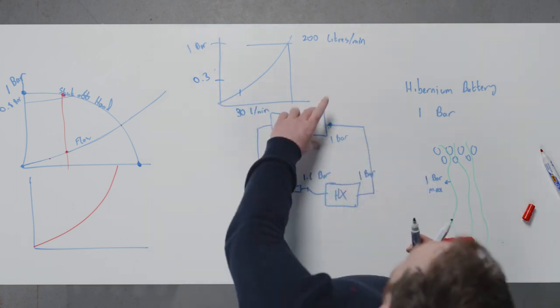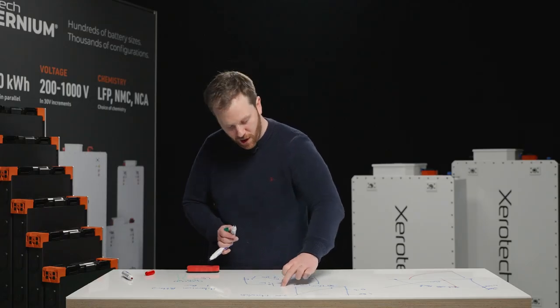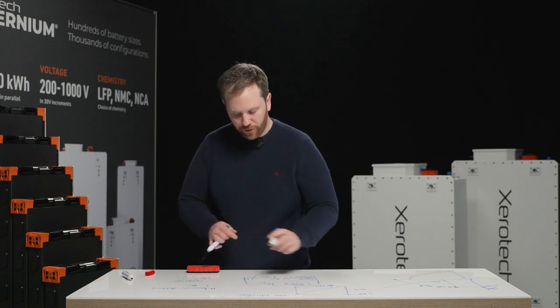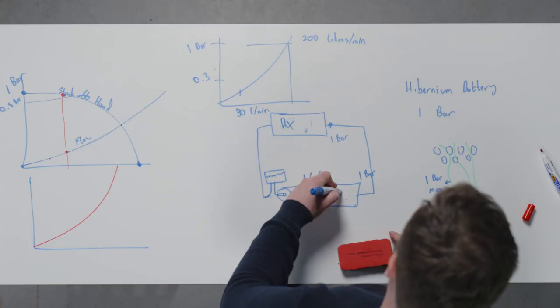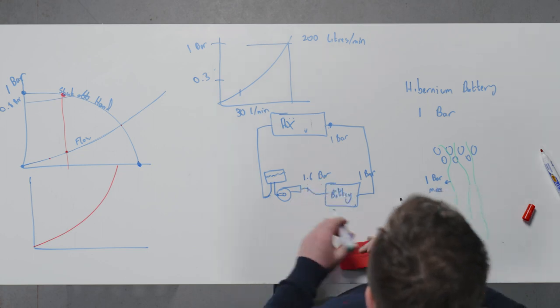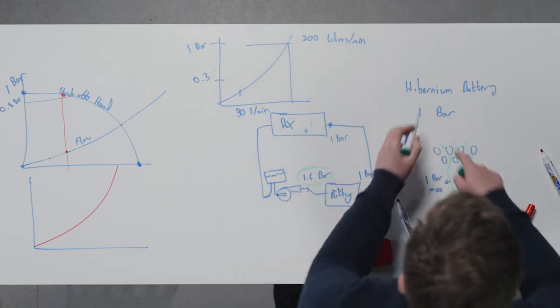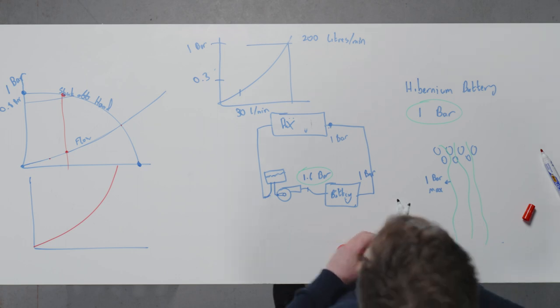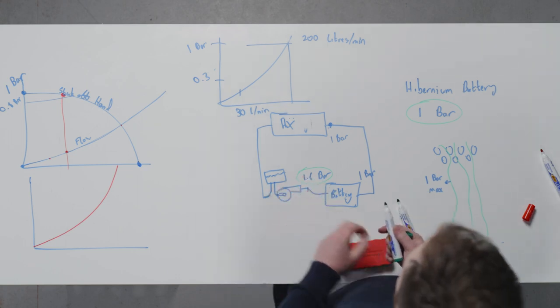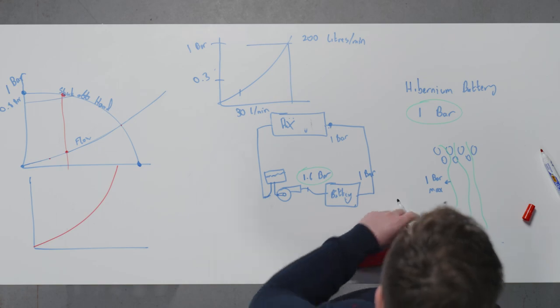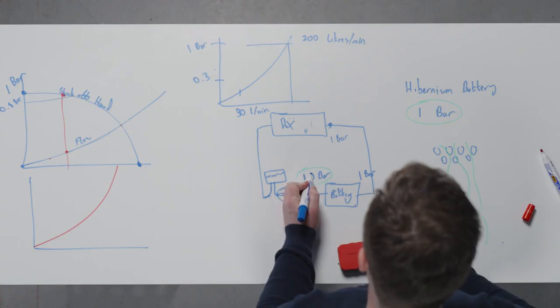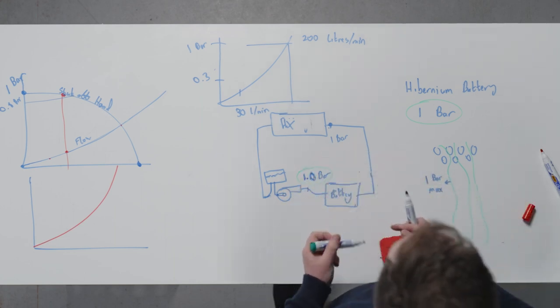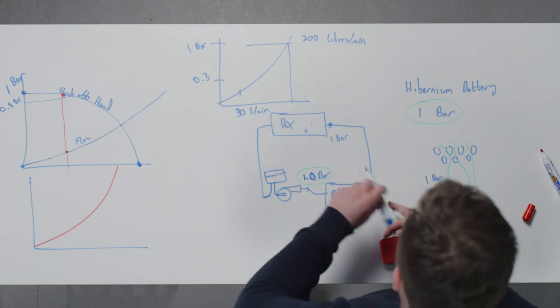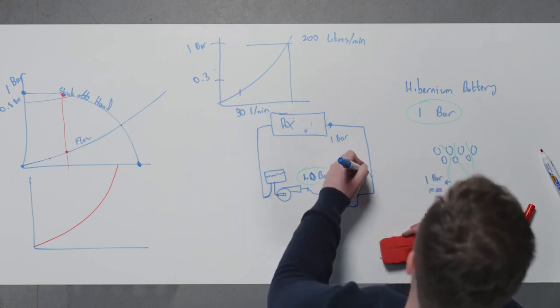And the difference of where you put this battery, if you put the battery here versus here, let's say we change this around now, that this is the battery. This is over our maximum pressure. This is not allowed. You can't do that. So you actually have to decrease the pressure that this can experience to 1.0 bar here. But the problem is that the pressure drop of the battery is very low. So the outlet of the battery is only going to be probably 0.7 bar.